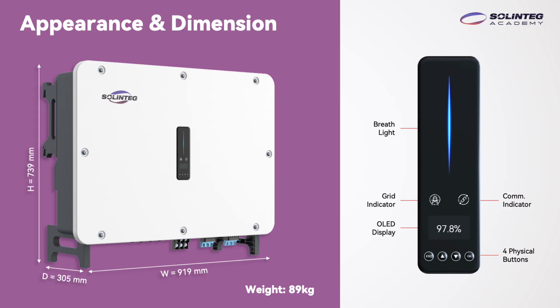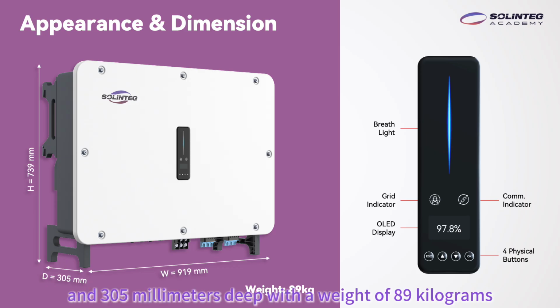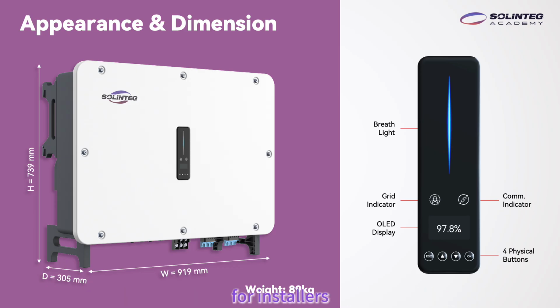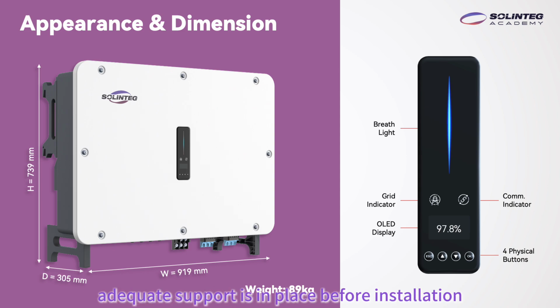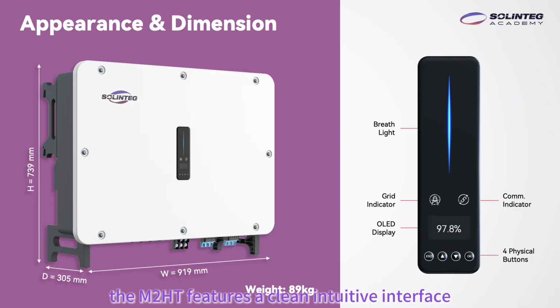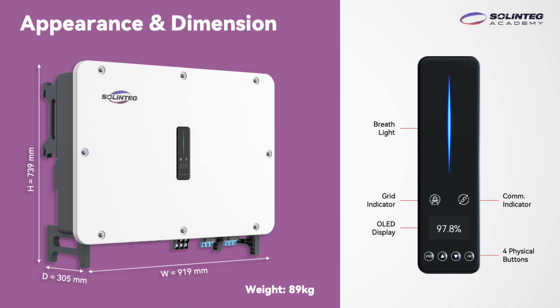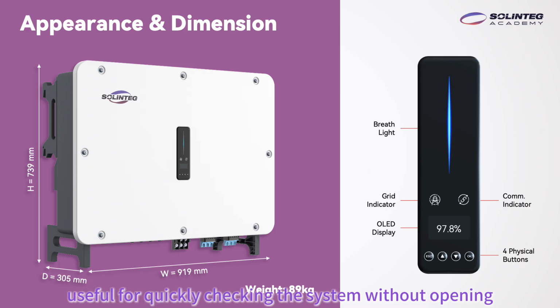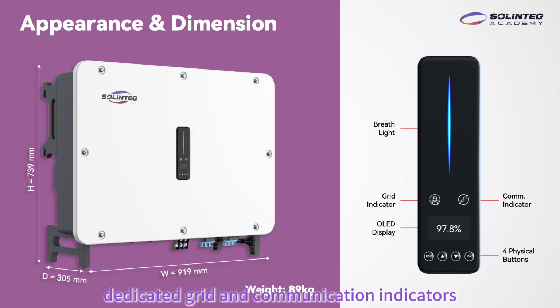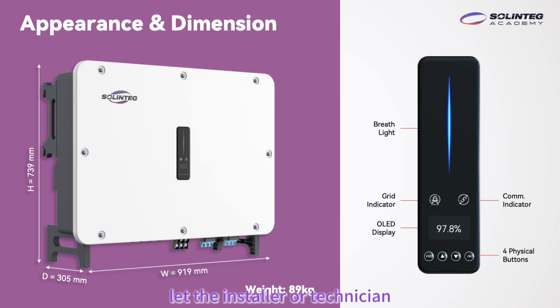The unit measures 919 millimeters wide, 739 millimeters tall, and 305 millimeters deep, with a weight of 89 kilograms. For installers, it's worth planning the mounting arrangement in advance and ensuring adequate support is in place before installation. On the front panel, the M2HT features a clean, intuitive interface. The breathlight gives an at-a-glance indication of the inverter's operating status, useful for quickly checking the system without opening any app or dashboard. Dedicated grid and communication indicators let the installer or technician immediately see whether the unit is connected to the grid and communicating correctly.